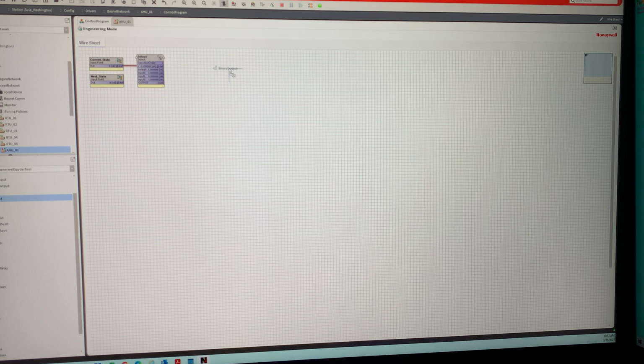So we're going to want to do a binary output for our fan start stop. So it'll be fan underscore start stop. What I do recommend for any controls guy out there is to come up with a basic verbiage on what you guys want to use when it comes to labeling all your blocks. So that way you have a consistency across the board, but then you can also save these programs and then modify them as you want to go, which is what we do a lot. We'll save them in a palette for all this stuff that I'm going to be doing with you guys. I will start off with a blank canvas so that way we can all see how things are started from start to stop.